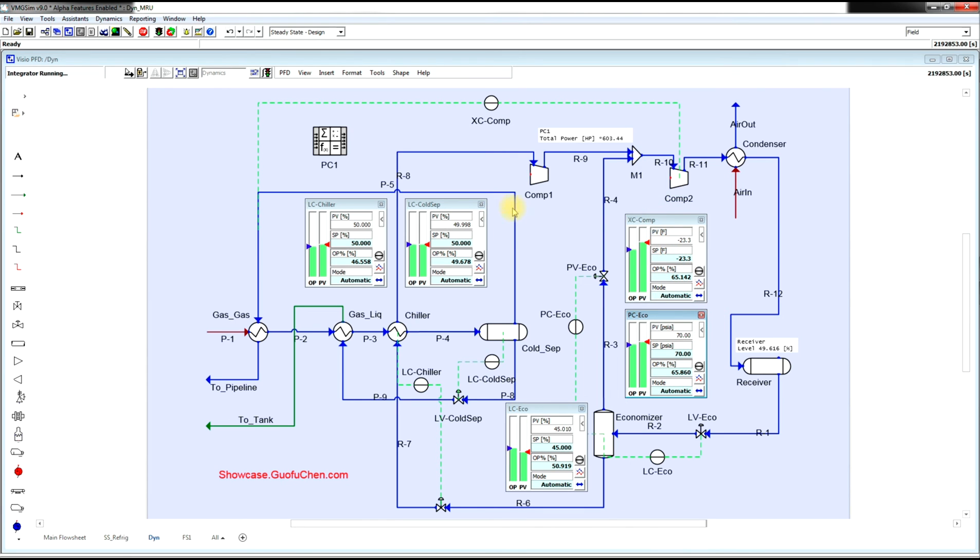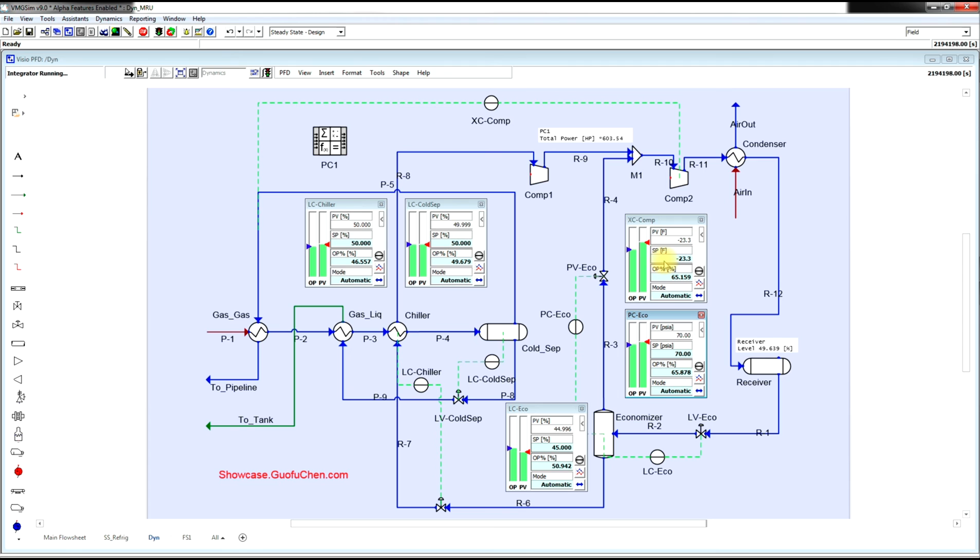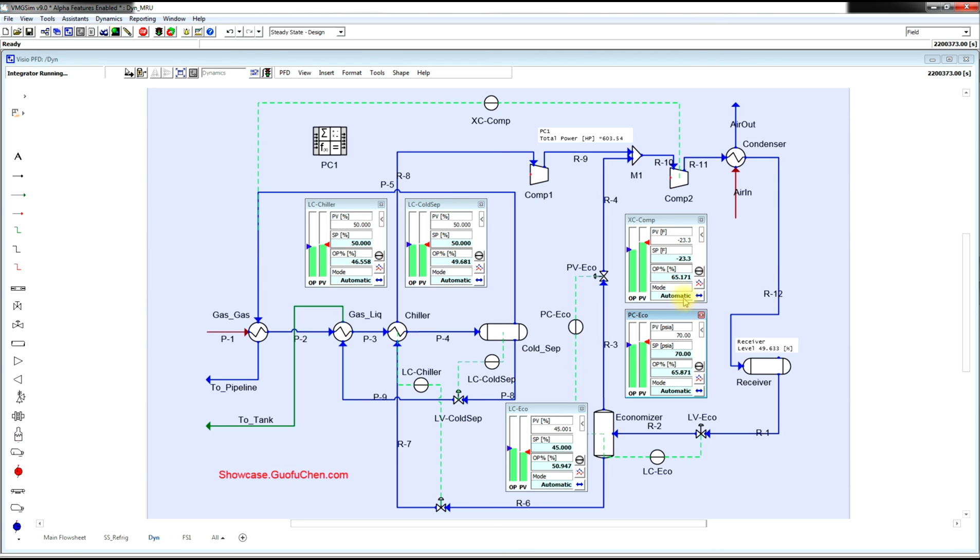The current cold separator temperature is about negative 23.3 Fahrenheit. What is the lowest possible cold separator temperature? Right now, the compressor is running at about 65%. How about we increase to 100% and see what's going to happen.